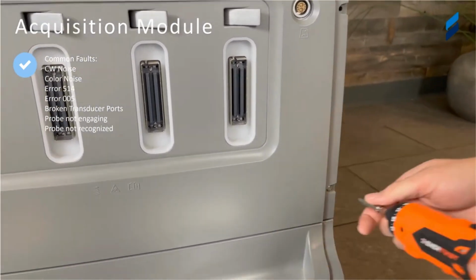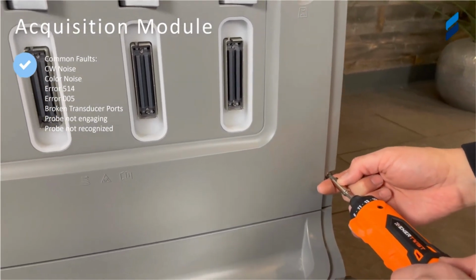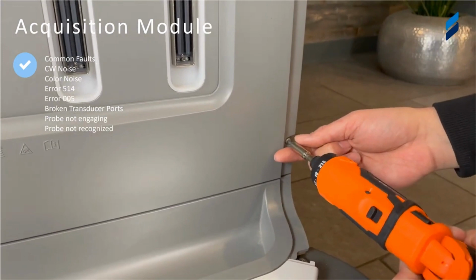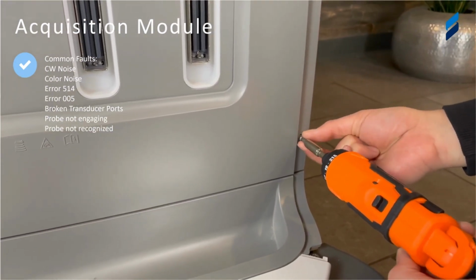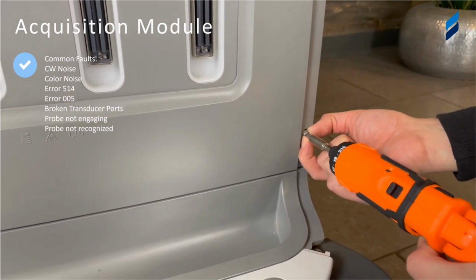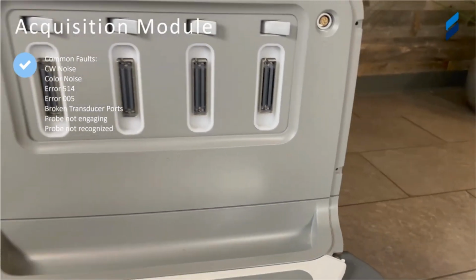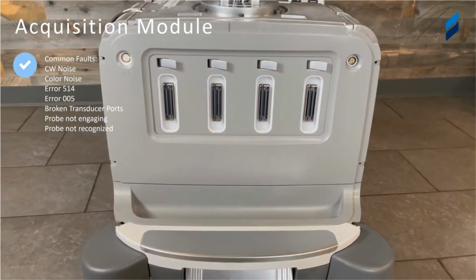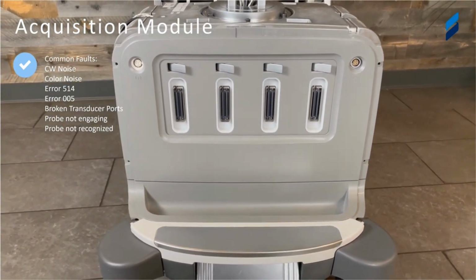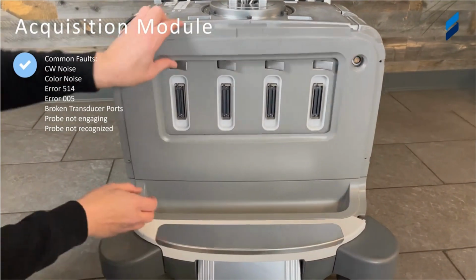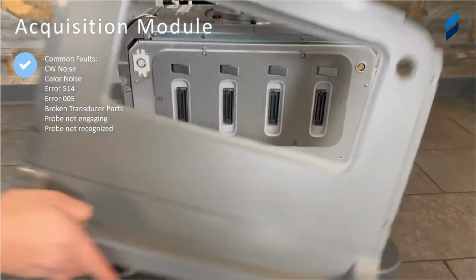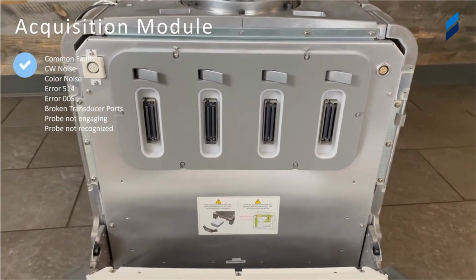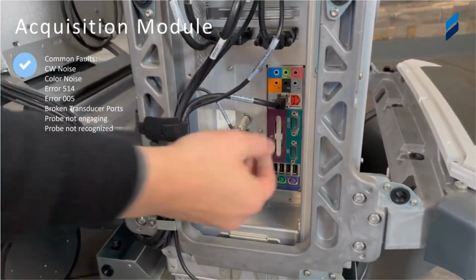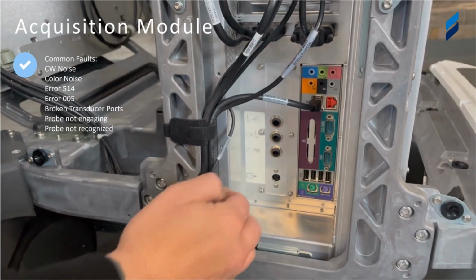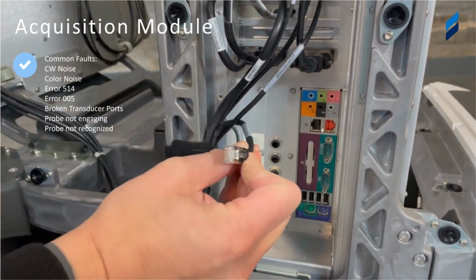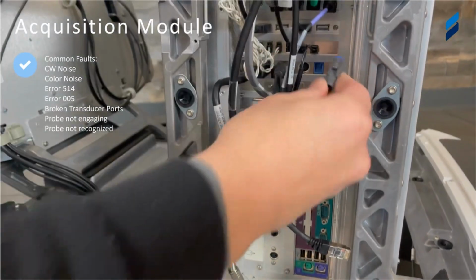You can see the transducer ports there. If you look at those closely, oftentimes, if you're having issues getting good connections in one port versus another, look at the port that's faulty and you might be able to see some broken connections in there on the interconnect. And we're going to remove this front plastic piece to get access to the metal assembly behind it, which will contain your acquisition module.